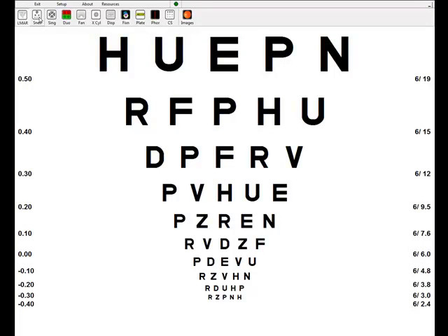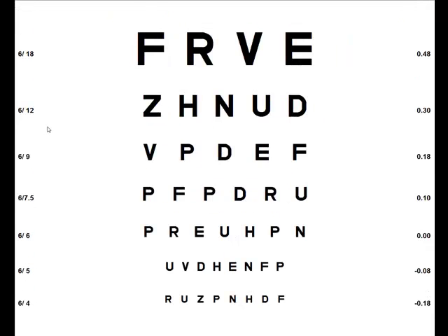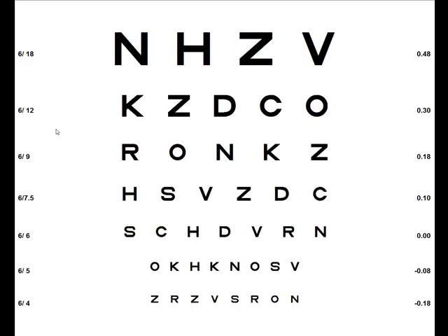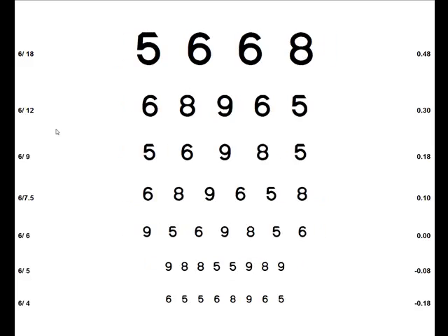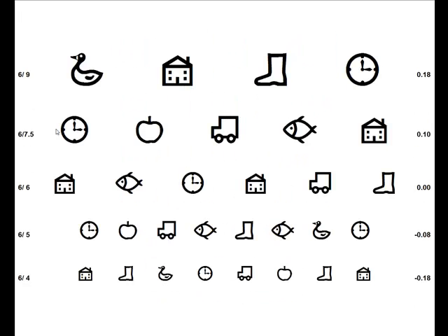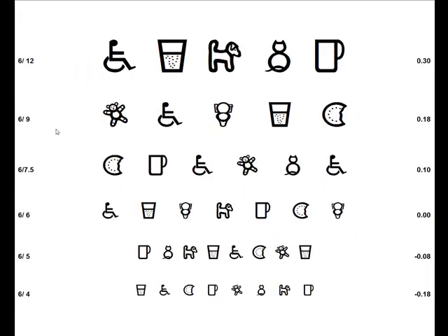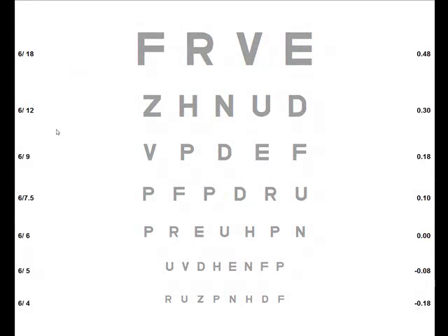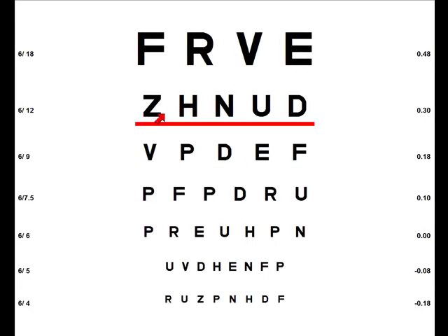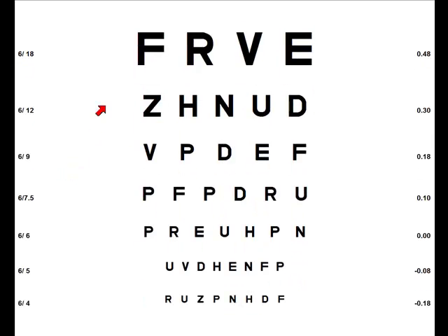Much of the same applies if you're in Snellen mode. You can see the arrangement of letters is different in Snellen mode, but the same applies. You can show a variety of different optotypes, vary the contrast, point at individual rows of letters, and of course increase and decrease the size. Everything I've shown you for the logMAR chart also applies for the Snellen chart.